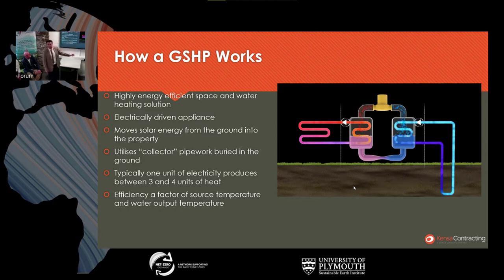We do it mostly by having 40 mil MDPE pipe. Now MDPE pipe is exactly the same material as your water supply pipe to your house, so it's just that kind of plastic blue pipe, but we tend to use a black pipe which goes into the ground. That can go vertically straight down to anything up to 300 meters, or it can go horizontally around a back garden or in a field, about a meter under the ground, and that collects the heat energy. So that's why we call it the collector, and that's really important when talking about heat networks and possibly district heating - the network doesn't create heat, it just collects it for the heat pump.